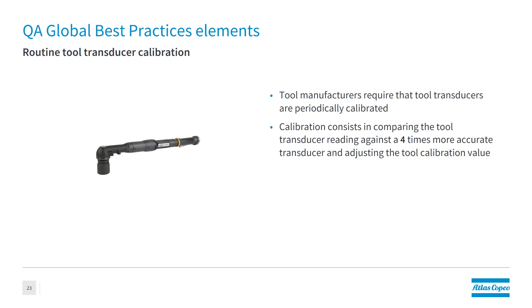So to calibrate a tool and do a routine tool transducer calibration, you need to read the reading from the transducer and compare it against something more accurate, usually 4 times more accurate. A solution here would be joint simulation benches, rotary transducers, and data collectors. With these tools, you can compare readings and evaluate a new calibration value so you can readjust the tool and be sure it's working as accurately as it's meant to.